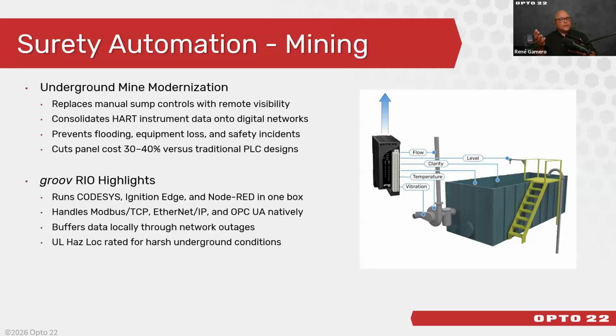In this case, they used CODESYS and an Ethernet IP scanner library that has the ability to talk to those. It has both the scanner and adapter, has Profinet, has CAN bus, J1939, a host of different licenses, BACnet, a host of different licenses. So those are two ways, besides using the core drivers from Ignition, also using these single libraries from CODESYS to be able to do that.